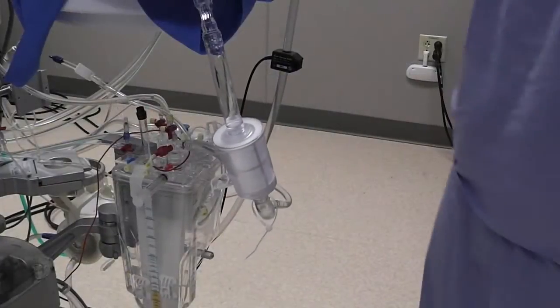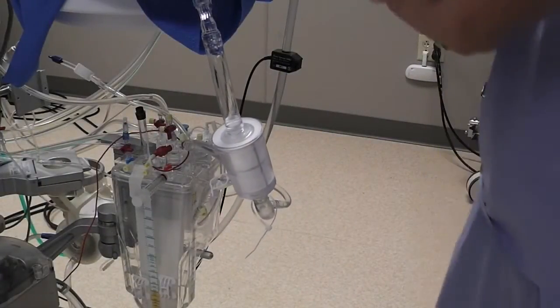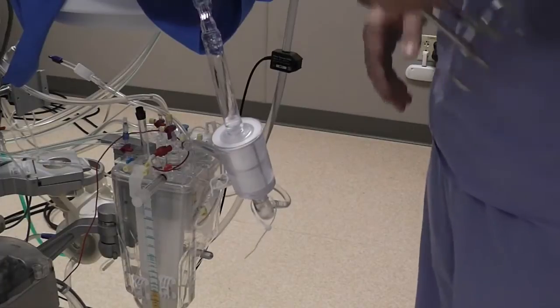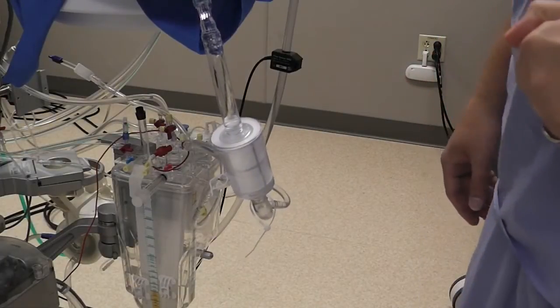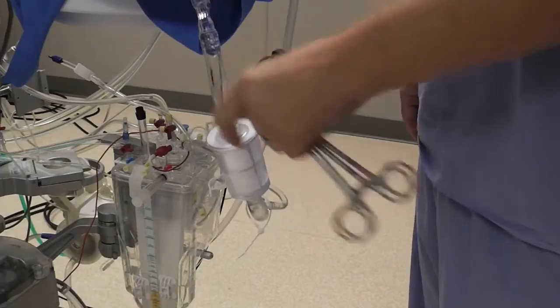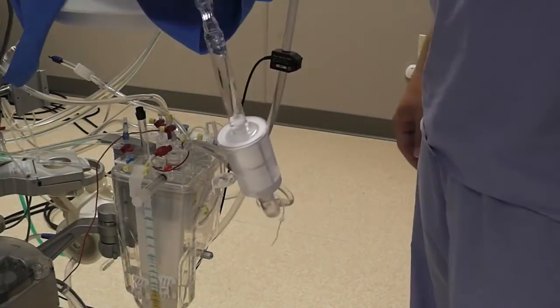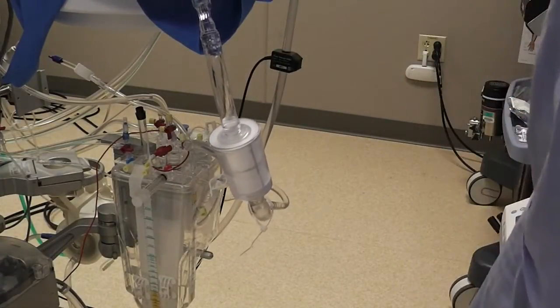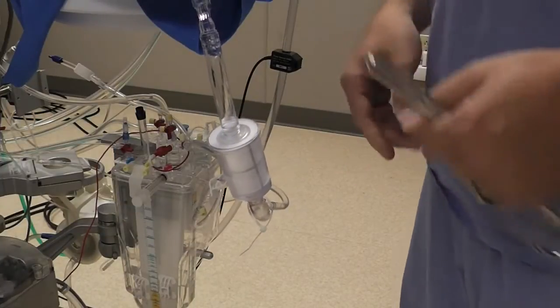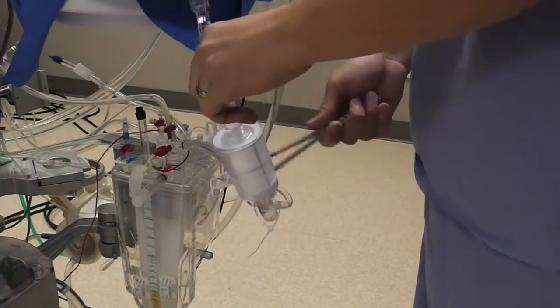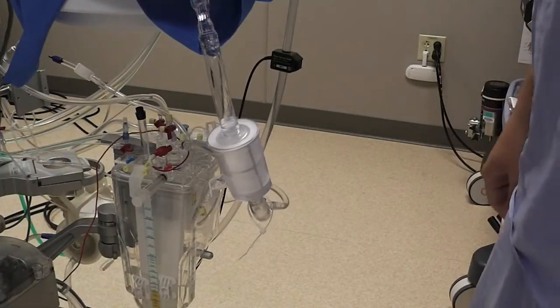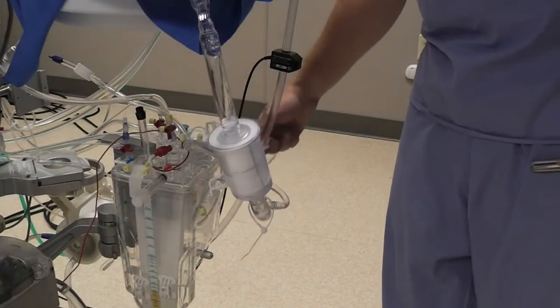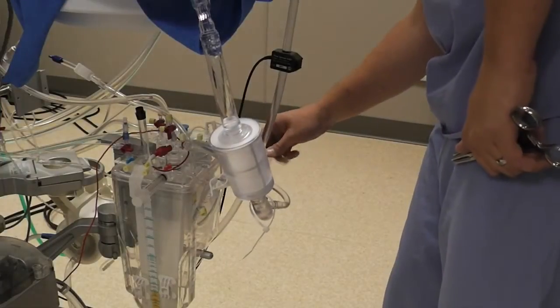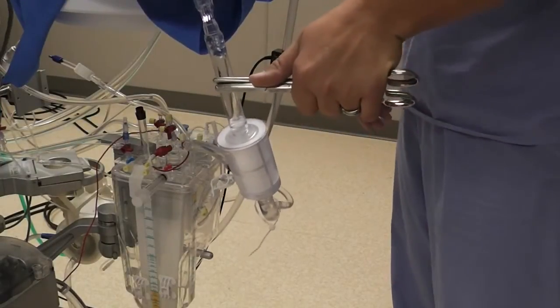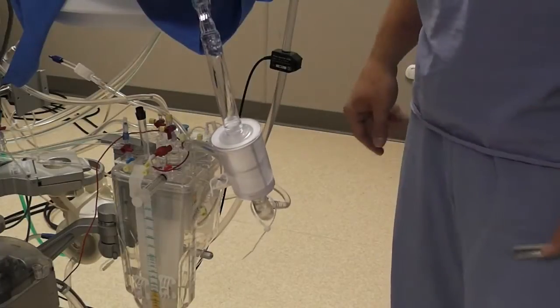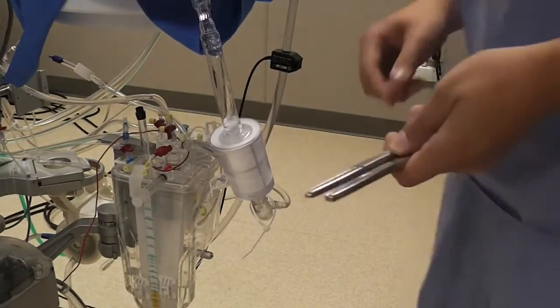Okay, I'm running out of time, as I said, so I might not be able to cover everything, and I'll try to cover some stuff that's a little bit more difficult for people. I'm going to remove this pre-bypass filter now. You want to let this run through the pump for, I don't know, half an hour if you can. That's not always possible, but if you can, let it flow through there for a while. I've slowed the pump down to about 3 liters a minute, and I'm going to open my recirculation line. That's very important because I'm going to occlude this arterial line. If that wasn't open, I would massively overpressurize the system. So open up that recirculation line.